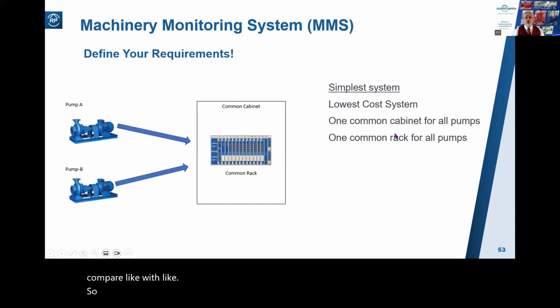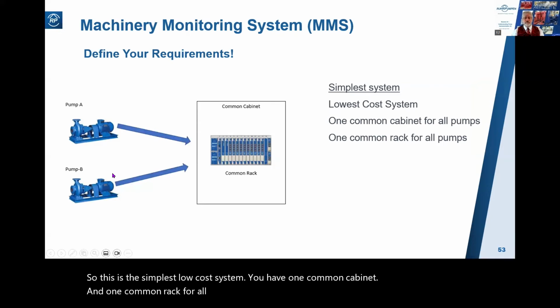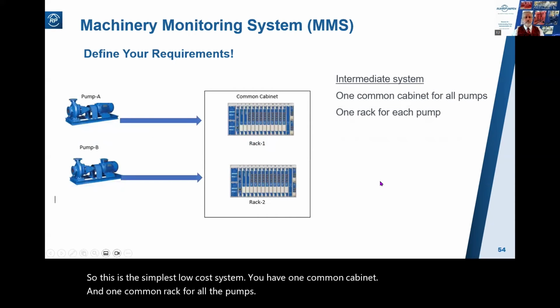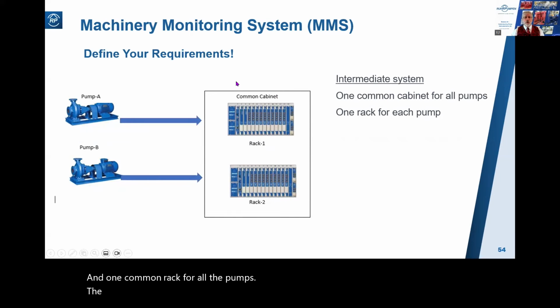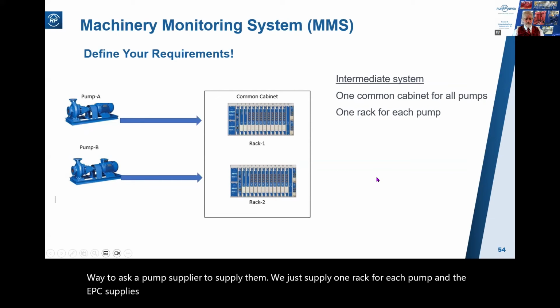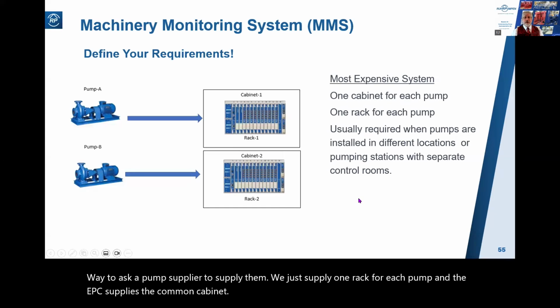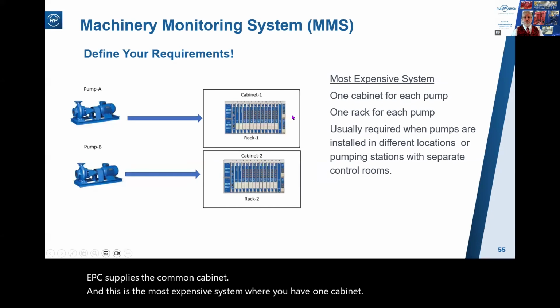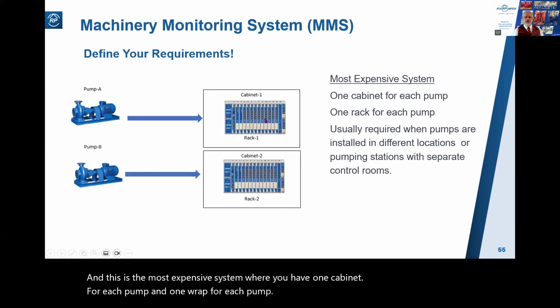So this is the simplest low-cost system. You have one common cabinet and one common rack for all the pumps. The intermediate system here: one common cabinet with one rack for each pump. This is probably the most commonly specified way to ask a pump supplier to supply them. We just supply one rack for each pump, and the EPC supplies the common cabinet. And this is the most expensive system, where you have one cabinet for each pump and one rack for each pump. This is usually required when pumps are installed in separate locations or separate pumping stations and with separate control rooms.